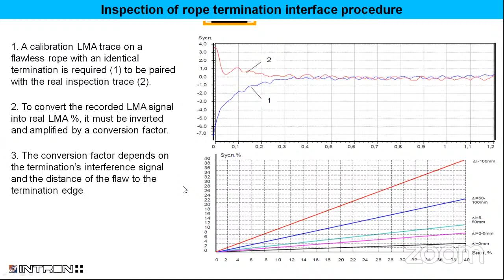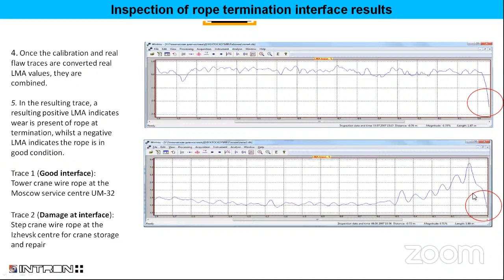We have a conversion factor, which inverts and amplifies the signal. Once this is combined, it is appended to the results. On a good rope, you will see the LMA decrease, and this is expected because you subtract it. But on a worn rope, even though you have damage here, look here, the zero point is actually off the scale, and it's still positive LMA, which means there's damage in this region.